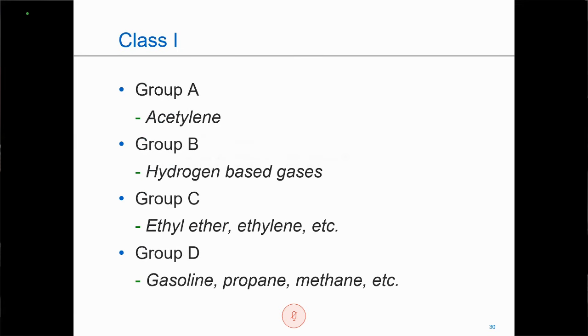And then we're going to look at our groups. Class 1 has Groups A, B, C, and D. A is acetylene. B is your hydrogen-based gases, 30% volume or higher. C is your ethers, your ethylenes. D is going to be gasoline, propane, methane. And you can actually make the argument that these groups are ranked in order of danger. For example, acetylene is easier to ignite and a much more forceful explosion than ethylene. Or hydrogen, for example, is going to be easier to ignite and a more forceful explosion than propane.